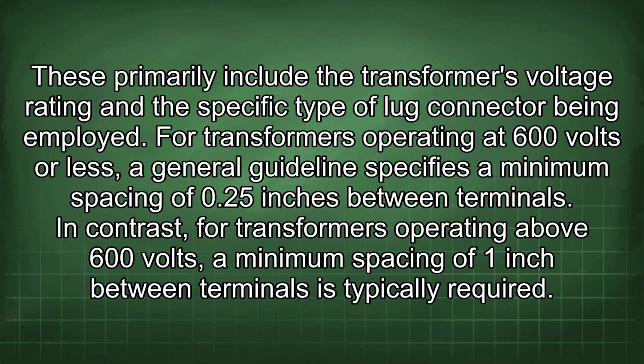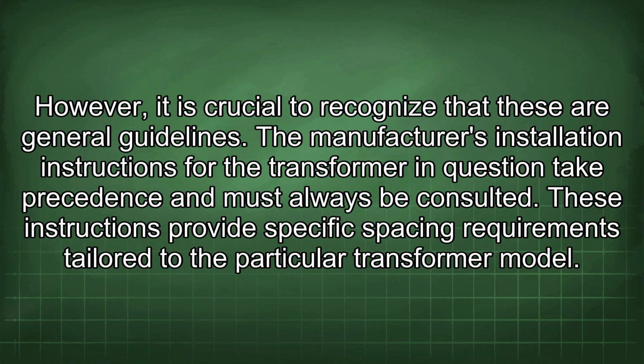For transformers operating at 600 volts or less, a general guideline specifies a minimum spacing of 0.25 inches between terminals. In contrast, for transformers operating above 600 volts, a minimum spacing of 1 inch between terminals is typically required. However, it is crucial to recognize that these are general guidelines. The manufacturer's installation instructions for the transformer in question take precedence and must always be consulted. These instructions provide specific spacing requirements tailored to the particular transformer model.